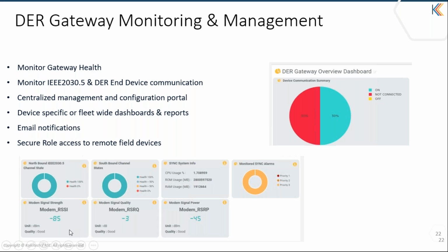And the modems, as I mentioned, there's an external modem, which is a GE modem, and we also need to monitor the network status, the network signal strength, signal quality, and the signal power. Those parameters can also be monitored from a central system through the dashboard. You can have a dashboard-based configuration, or you can have configured reports, and it will generate a report on a daily or weekly basis, as per user configuration. And the reports can be sent out as an email, as a PDF or an Excel file, to configured recipients.